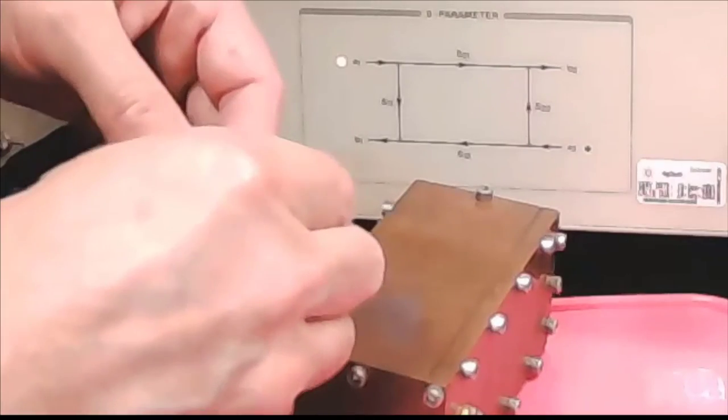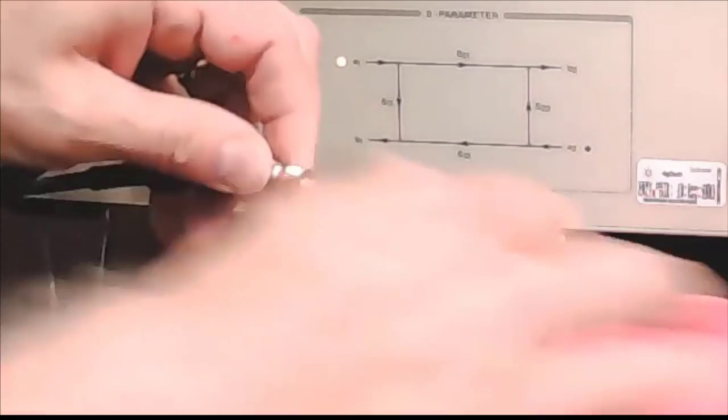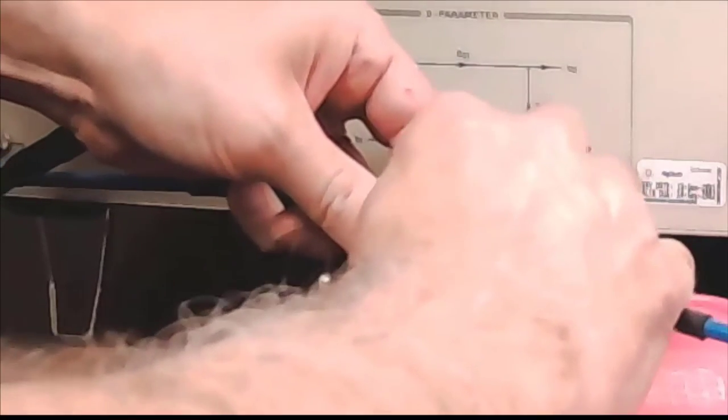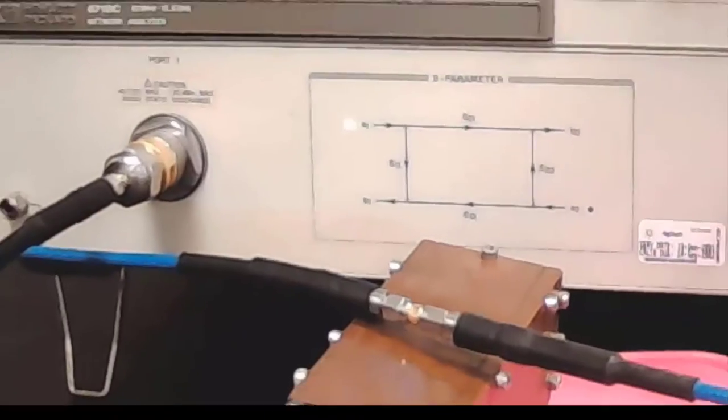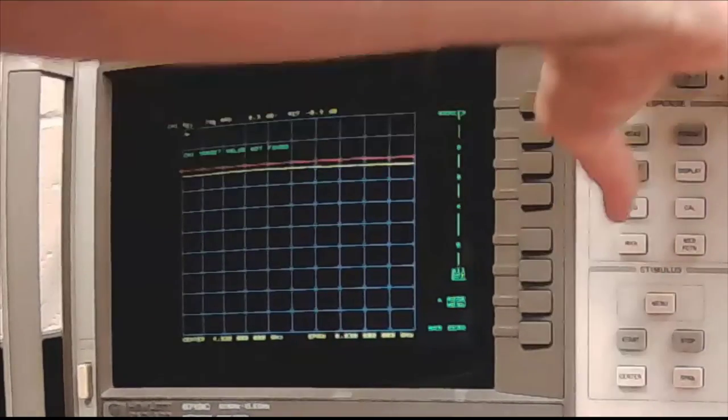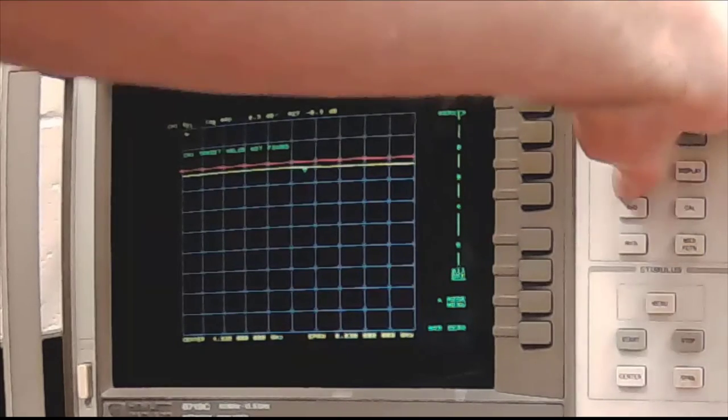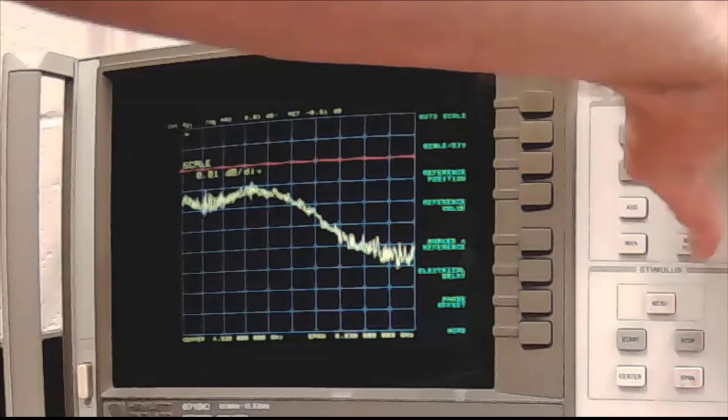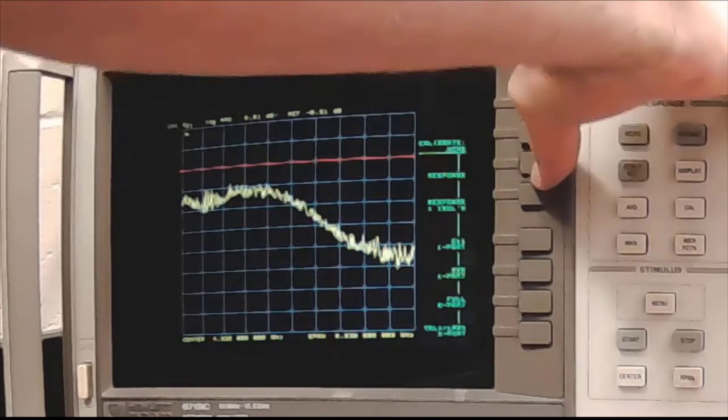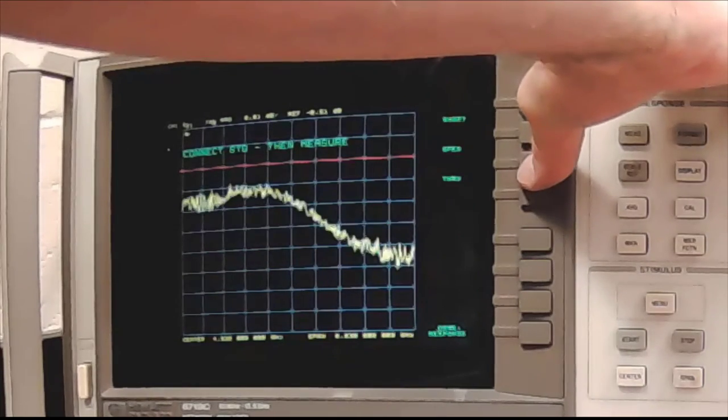Now replace the resonator with an SMA bullet. And one thing I would comment about as you attach components like these adapters. Always turn the nut of the connector and not the component itself. You don't want to scrape the gold plating off the pins and sleeves. Check that all connections are tight. Turn off the markers. The trace is not exactly horizontal or straight or at zero. I'm going to calibrate it out. Calibrate. Calibrate menu. Response.